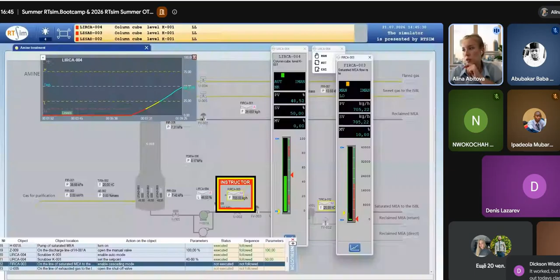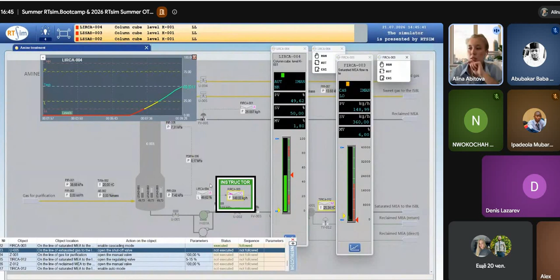After that, it's already opened. Okay, to turn it to cascade mode, we move to the operator's field. Let's turn it to cascade mode so that they will work like hands and eyes, as I already mentioned. LIRC4 as a level device will measure the level in the column, and FIRCA3 device as hands will control the valve.